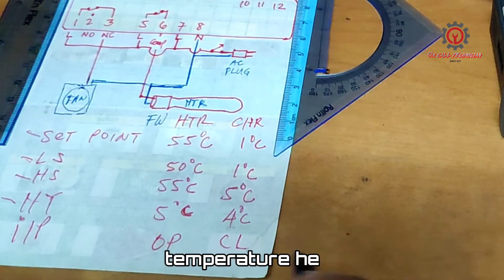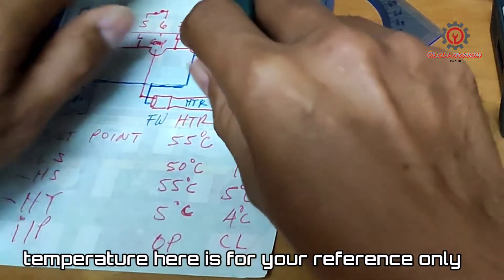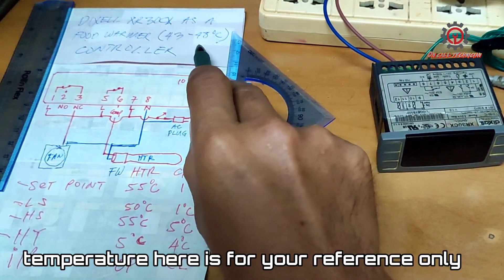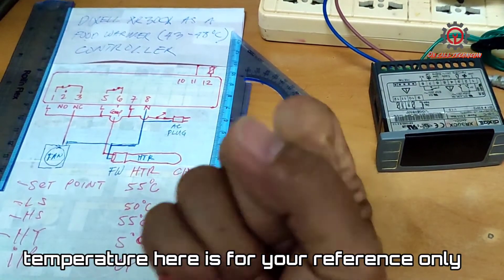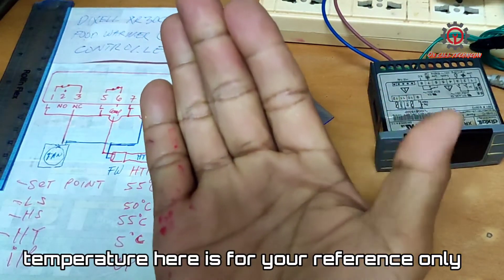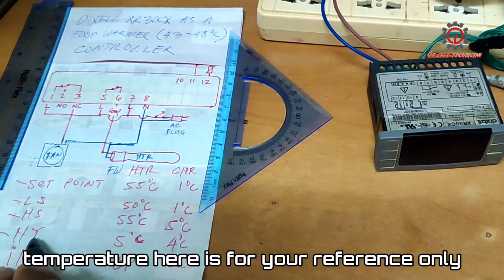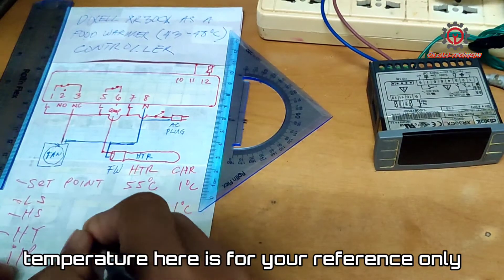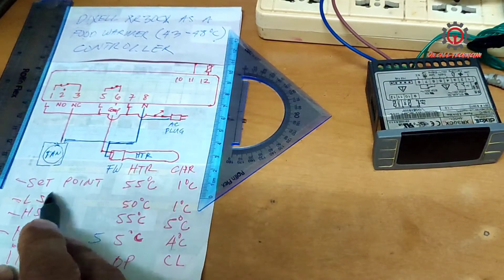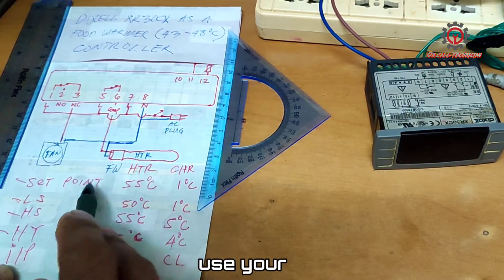For the set point, take a look: we have 43 to 48 degrees Celsius. That gives us a differential of 5 degrees Celsius for our HY parameter, which remains at 5. So our setpoint should be 48 degrees Celsius.